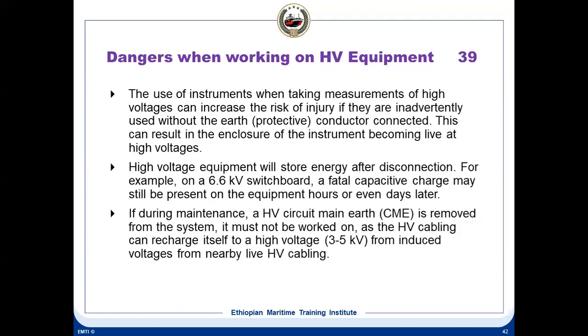High voltage equipment stores energy after disconnection. For example, on a 6.6 kV switchboard, a fatal capacitive charge may still be present on the equipment even after days. So even if you switch off, it can hold charge, because the cable is like a capacitor. It can have some charge in it, so this has to be discharged immediately. If you leave it idle, it will also take time to discharge. If during maintenance an HV circuit is removed from the system, it must not be worked on, or the HV cabling can recharge itself to a higher voltage from the voltage induced by nearby live HV cabling. So because of the nearby cabling, it can get recharged again.